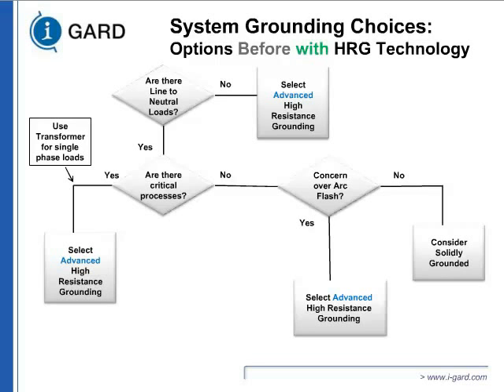Now if you have a high-resistance grounding system and you use a 30 kVA transformer, for example, for lighting, you can see you're making systems safer by design. One of the concepts all designers should employ, or do employ, is system safety by design. So you cut down the potential. You can use high-resistance grounding for critical processes and then use a smaller transformer for your lighting or any other single phase load. If you're concerned about arc flash, and who shouldn't be, arc flash is a very dangerous condition that, like the name implies, burns people. So you use an advanced high-resistance grounding system.